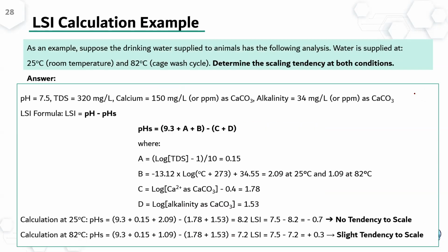Okay, so we move on to the LSI calculations. So what is LSI? LSI is the Langelier Saturation Index. It tells us whether the system will generate scaling or not. So we can see in here an example of the calculations of the LSI.